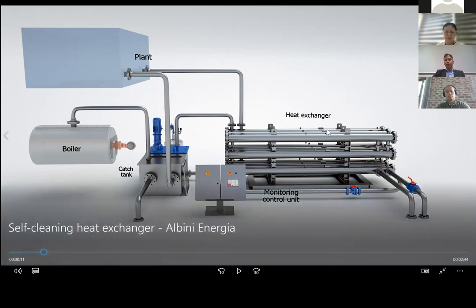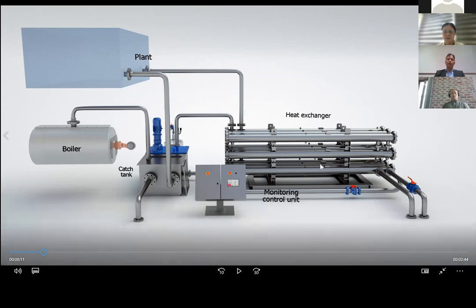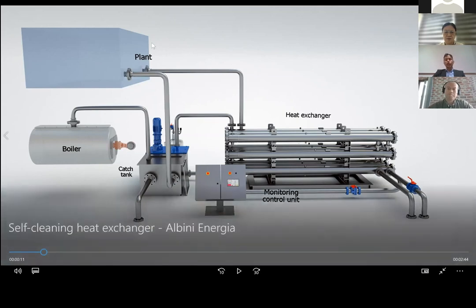The second part of the system is the heat exchanger, of course. As I told you, this heat exchanger can be done with a pipe shell heat exchanger, which is the best solution if your wastewater is full of suspended solid. Basically, the wastewater goes from the plant to this collection tank and is pumped through the heat exchanger.